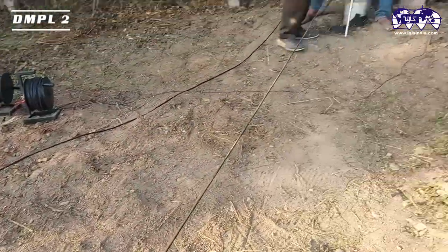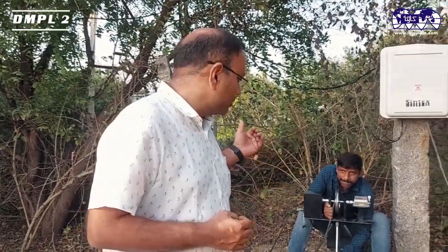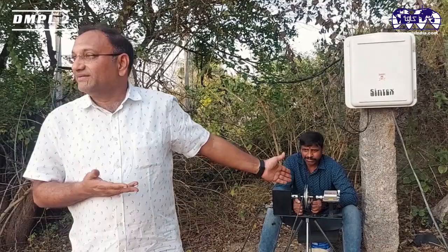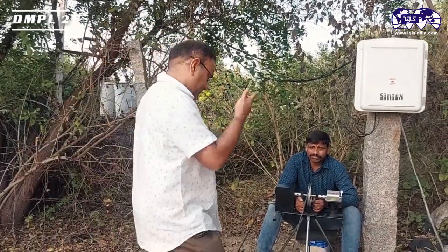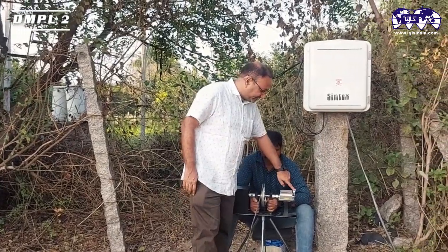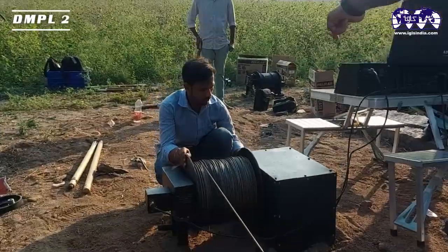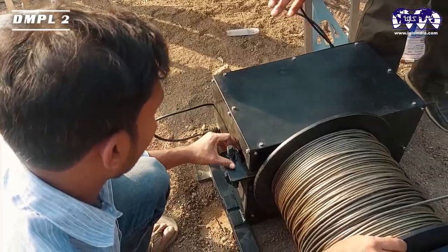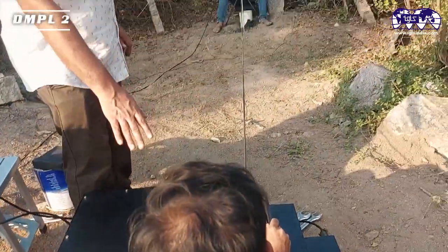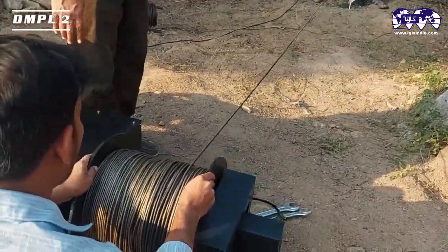Now, usually logging is done in a fresh borehole to construct the tube well. Here, for the sake of demonstration, we have taken an existing borewell and are making use of it. So I am lowering the probe into the bore. In the case of a fresh borewell, the contractor will give you the depth of the bore being dug. Here I know the depth. It is around 60 meters. Now I am lowering the probe. Before I do, I set it to 0, and my team member has released the lock to loosen the winch mechanism and is slowly lowering the probe.